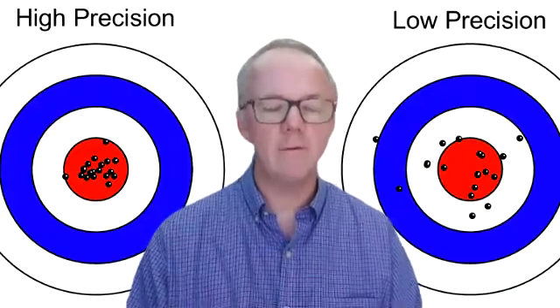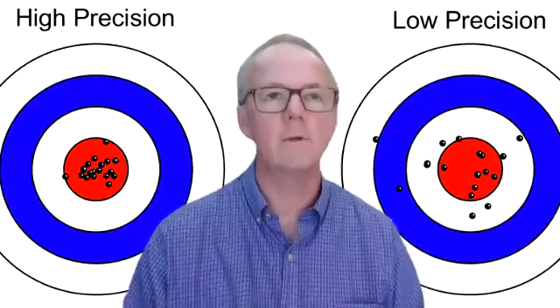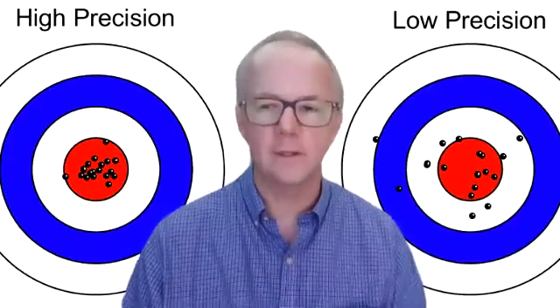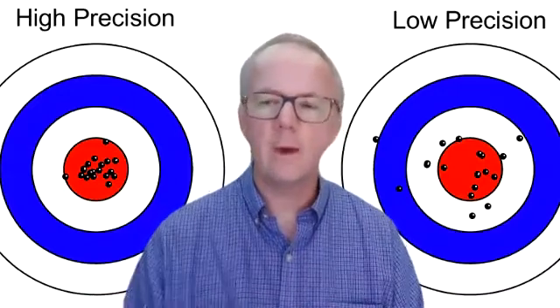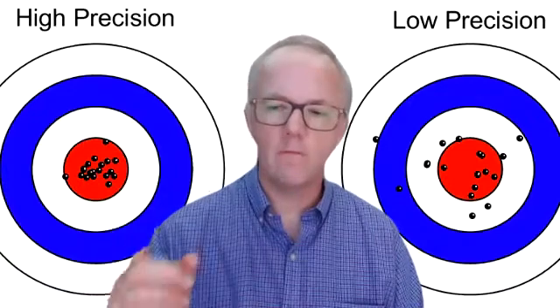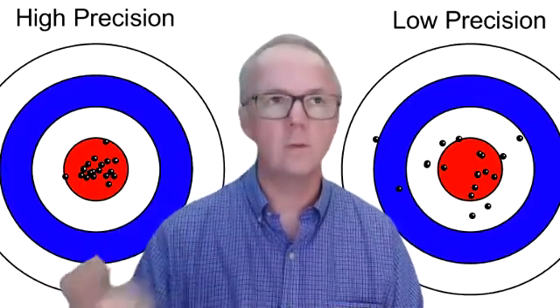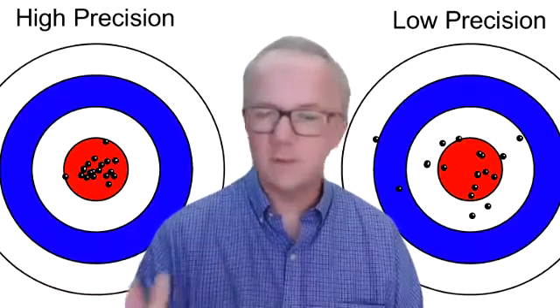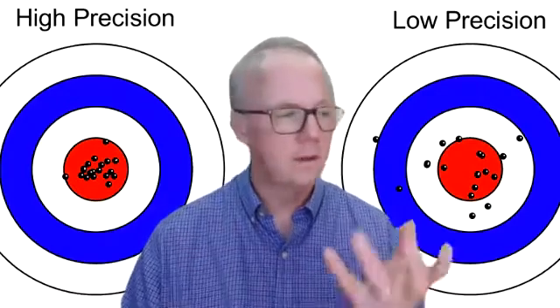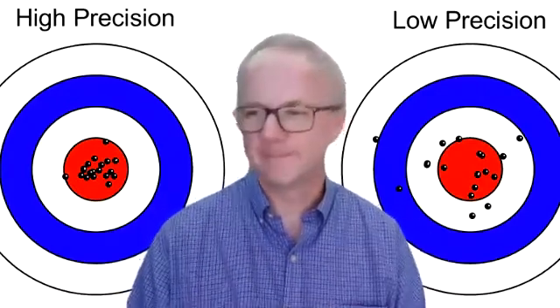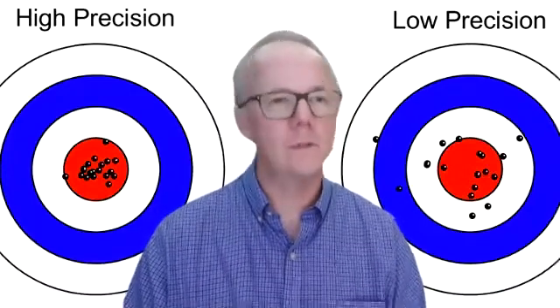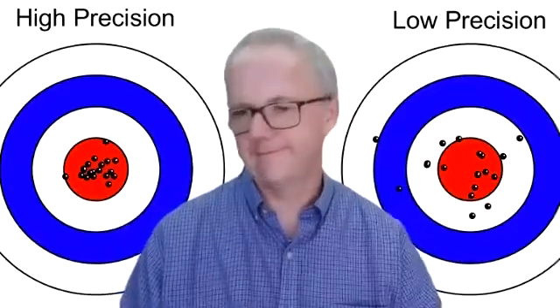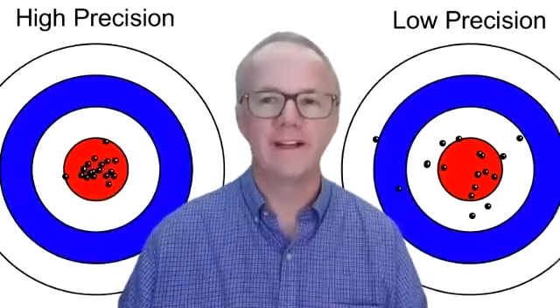Be really careful that you understand what you're looking at when you're looking at data — it's not just calibration. When you're looking at data, think about what it really means. Does that one result mean you've got good precision, good accuracy, good linearity, good reproducibility? Then you can do your validation work as well as your calibration. To summarize: high precision means keeping results tight together; lower precision means they're spread out. That's it for me for today — it's Paul Palmer, talk to you soon.